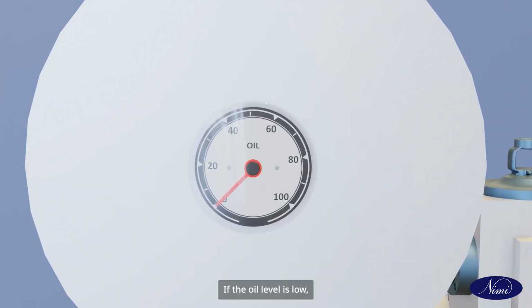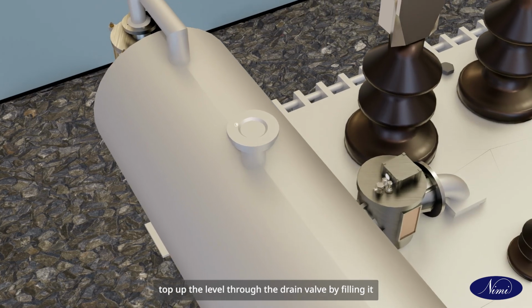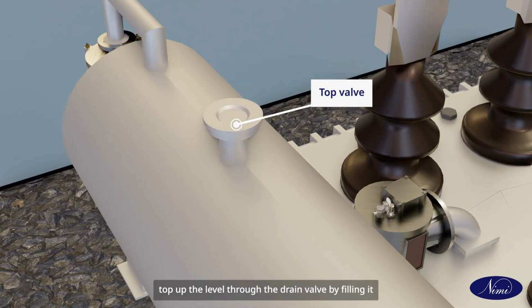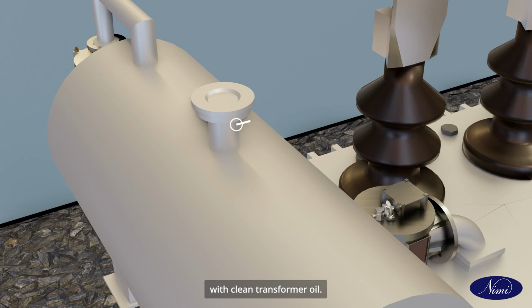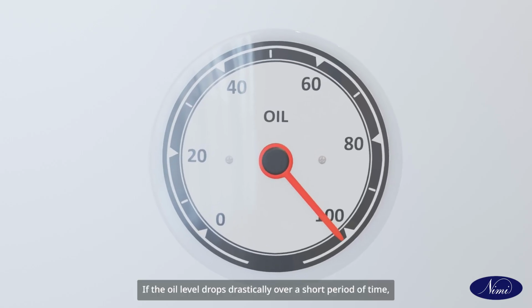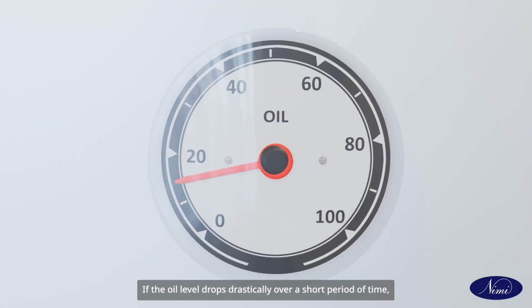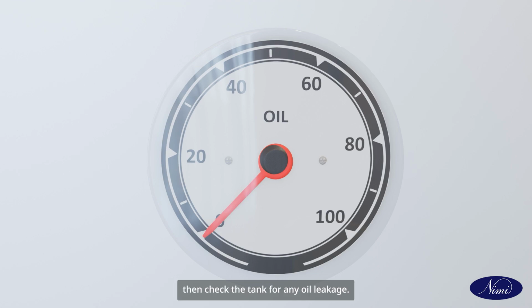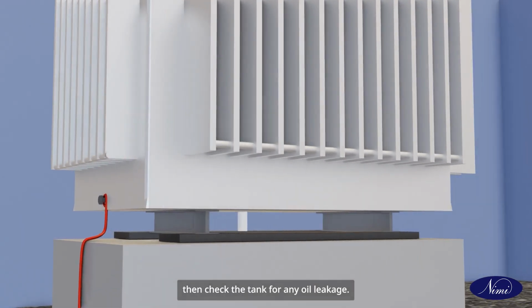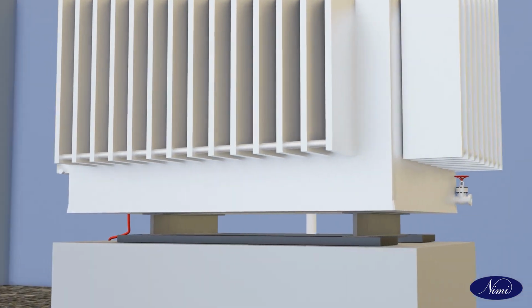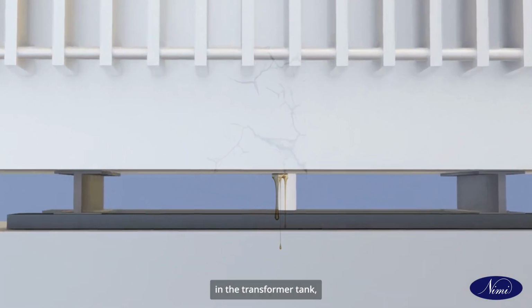If the oil level is low, top up the level through the top valve by filling it with clean transformer oil. If the oil level drops drastically over a short period of time, then check the tank for any oil leakage. If there is a leak in the transformer tank, take suitable action to prevent leakage.